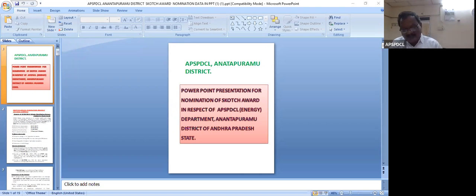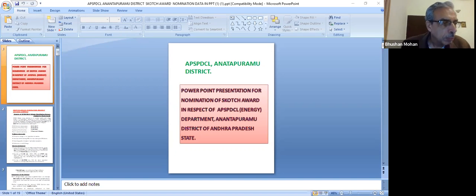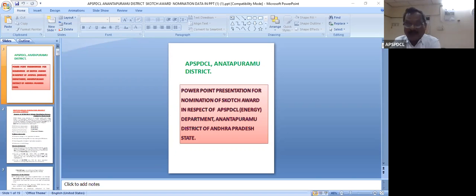To avoid these things: the general practice of any discom is to lay 11 kV lines from the 33 by 11 kV substation, erect a 3-phase 11 kV to 400 volts transformer at one convenient location, and lay long LT lines up to the nearest load center to the consumers. Because of that, poor tail-end voltage occurs at consumer motor terminals, there are high technical losses due to the greater length of lines, and more scope for theft of power, so frequent jumper cuts and fuse blows.